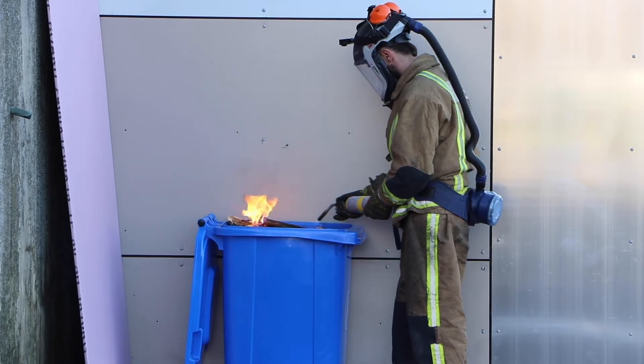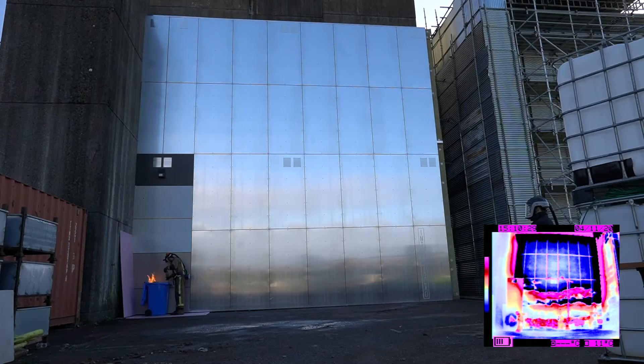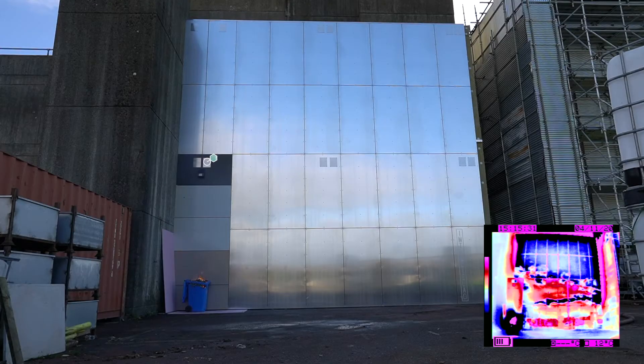The product recently underwent testing with the Fire Protection Association, who simulated a dangerous fire in a high-risk building using a specially built cladding wall fitted with 12 internal and 1 external IntelliClad sensors. The first alarm comes from Sensor 2, located in the bottom left corner of the cladding wall, 5 minutes and 9 seconds after ignition.